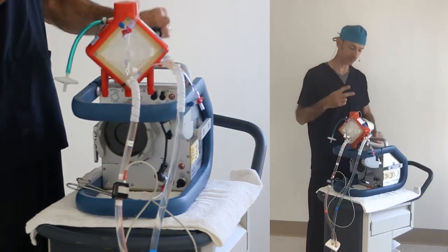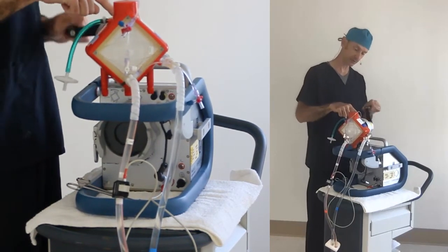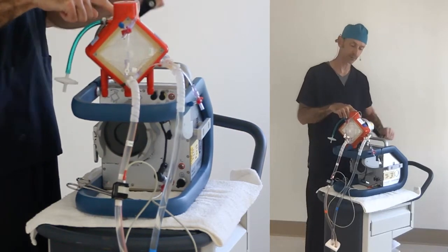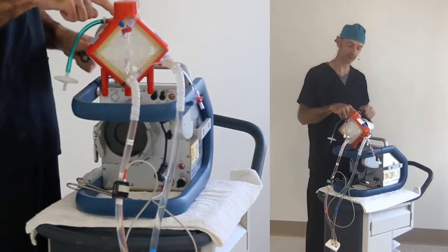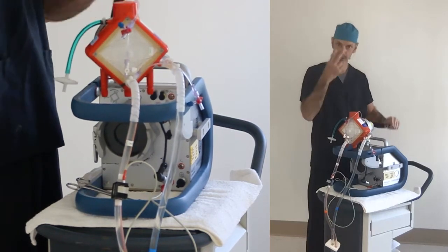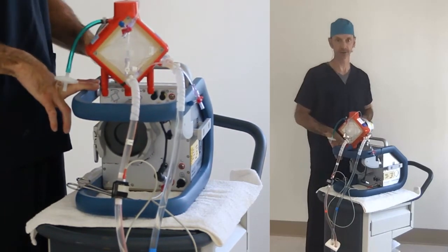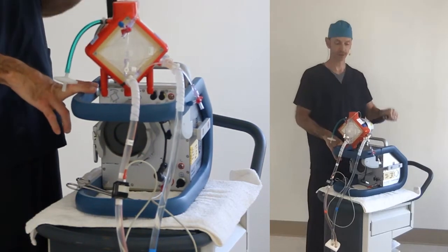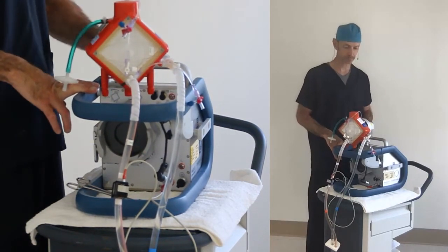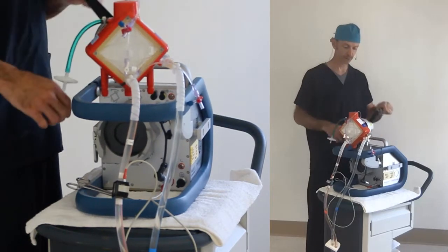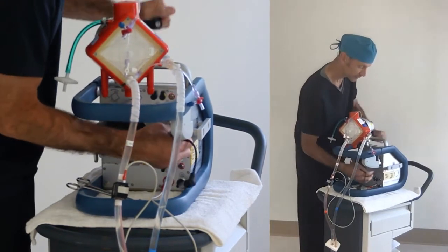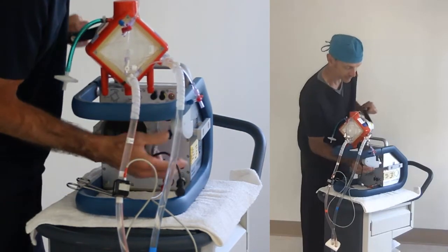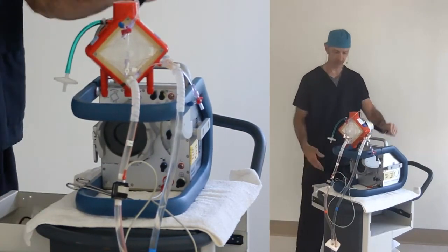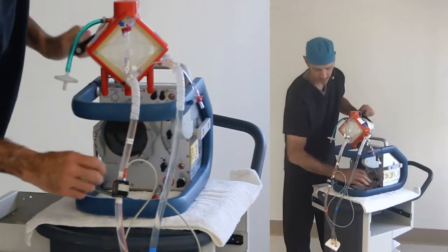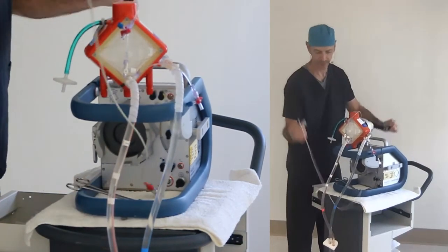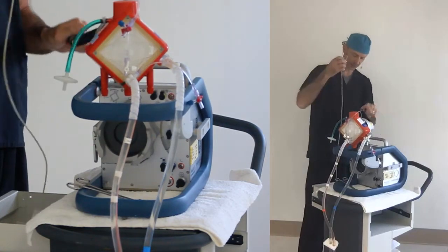You show them 2 things. You crank this knob, to hold this green light right there at that number you tell them. I'm using 3,000 RPMs. 3.0 is what it says up here. And then watch the patient's pressures and saturations. Talk to the nurse. The nurse knows what this patient needs. Okay? So that's what they're doing. In the meantime, I've snuck around and disengaged just about everything. Just thrown it back in the box. And they're going to have to reassemble it, because in a moment, magically, their new pump is going to enter the room.